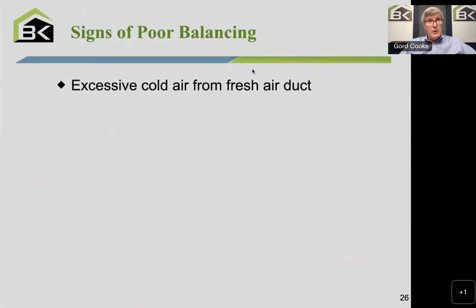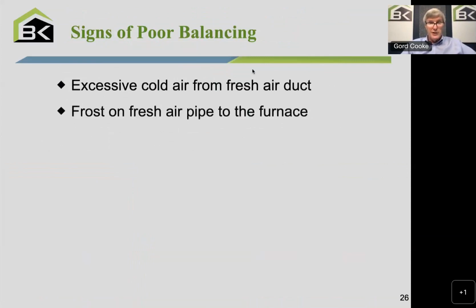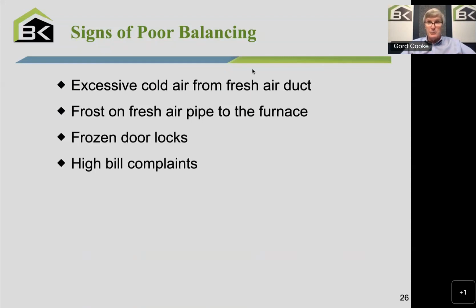And I mentioned if you have poor balancing, the signs are that you'll feel excessive cold air coming from outside. You're not getting proper energy recovery. Or if you see frost on the fresh air pipe that's running from the HRV to the furnace, the non-insulated piece, that would be an indication of poor balancing, where I need to check on that. Or if you have constant frozen door locks on the house, that means the house is under positive pressure and the warm, moist air is going out through the door locks and freezing. That's a good sign that your HRV is not properly balanced. Or if you get high bill complaints, I said it should only cost in the order of $100 to $150 a year, both the electrical cost and the heating cost.